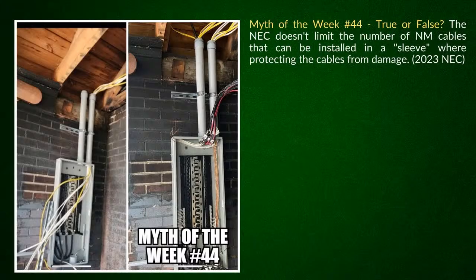So, to me, the thing that's funny about this was the AHJ in this case actually gave him a rejection based on 334.80, which is more than two current carrying conductors, more than two NM cables penetrating through a wood hole and sealed with thermal insulation. So that's not even close to the same as what is going on. I agree with the gentleman that just decided to appease the inspector and change this out. But this could have very easily, I think, been corrected and not been a code violation. And I'm sure you're gonna take this way further than I just did, King James. Yes, I will.